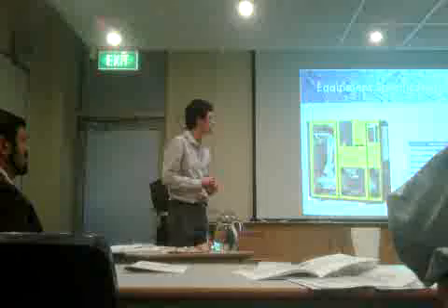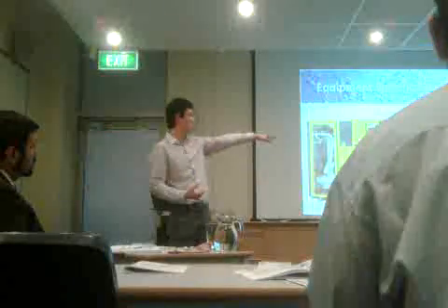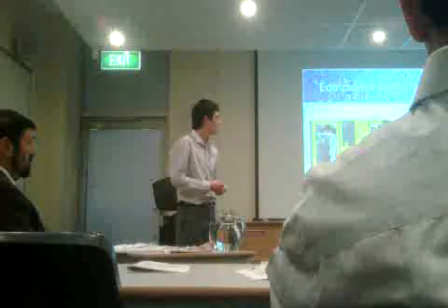The next equipment I would like to talk about is the compressors. We selected screw-type air compressors in this case, and notice that we have a very high maximum discharge pressure. This high discharge pressure affects the compression ratio as well as the discharge temperature. I'm going to talk a little more on this in the parametric analysis section. Also note the efficiency values. Typically for a compressor or a pump, the efficiency ranges between 50 and 70%, according to Coulson and Richardson's Chemical Engineering Handbooks. In this case, I'm just putting the average value here.